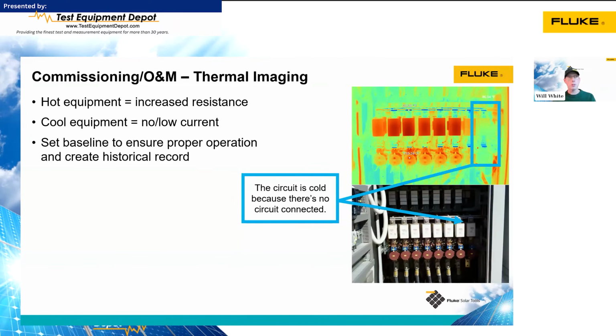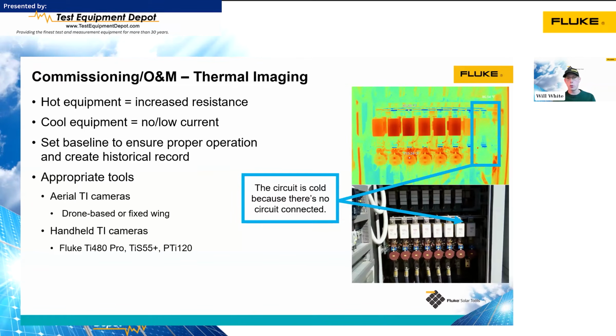Doing thermal imaging at commissioning allows us to set a baseline, so we know things were working properly when we installed the system. We can go back to that in the future and see if there's been any changes. You can use aerial thermography. There are many drones on the market with thermal cameras. At Fluke, we have a whole range of thermal cameras, from the small PTI 120 pocket camera that goes for around $1,200 up to the high end, the TI 480 Pro, which is a much higher resolution, and it runs about $12,000 or so.